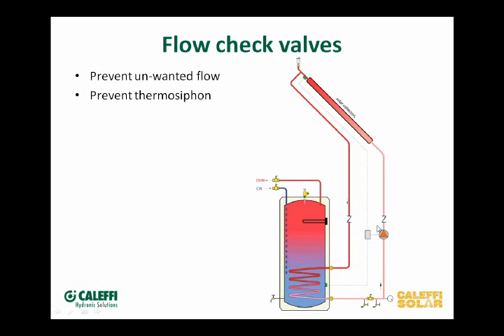The check valve should be rated for that temperature, because it's going to see that slug of high temperature after the panel stagnates. When you pick a check valve, look for one rated for solar temperature.